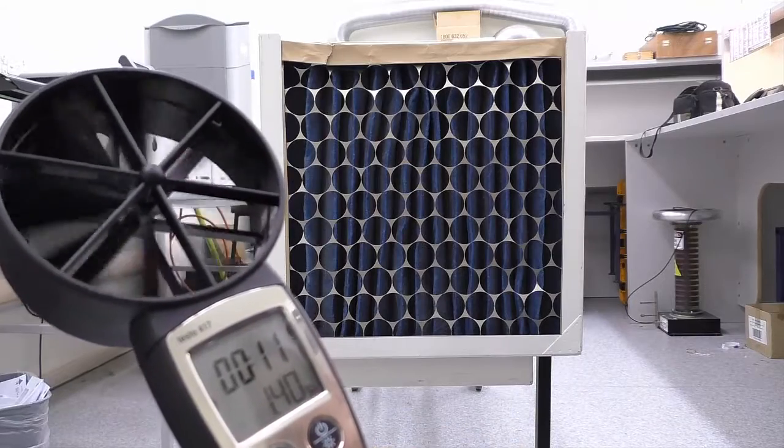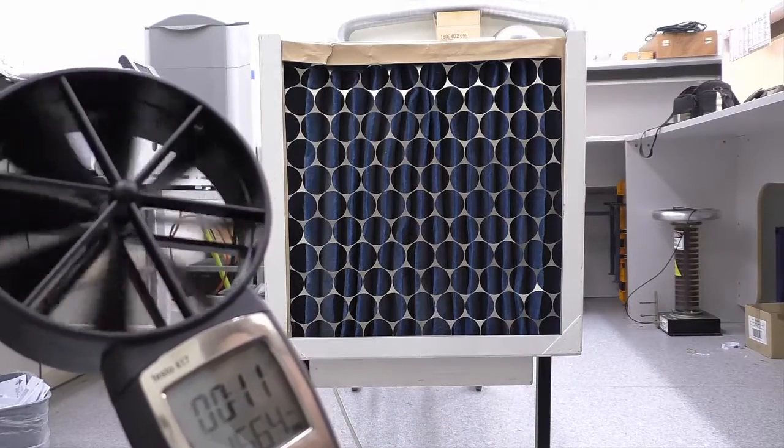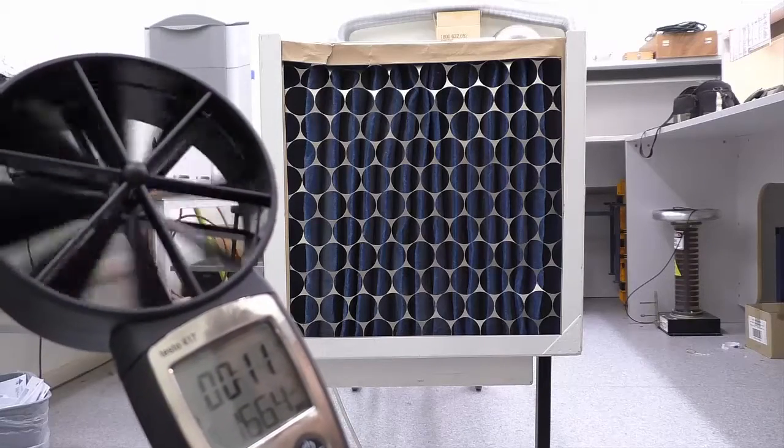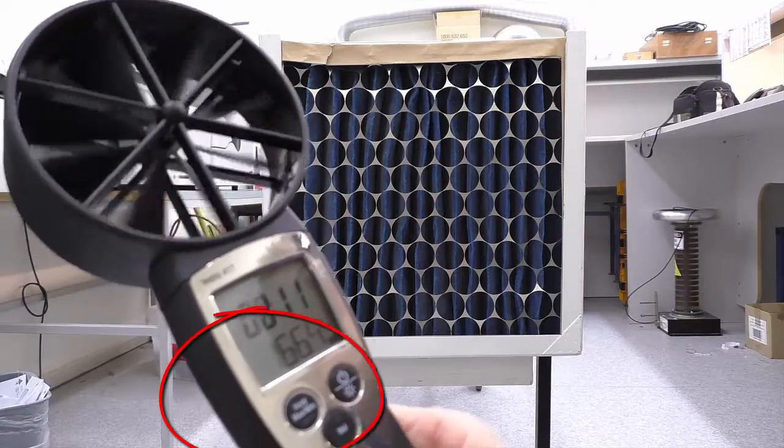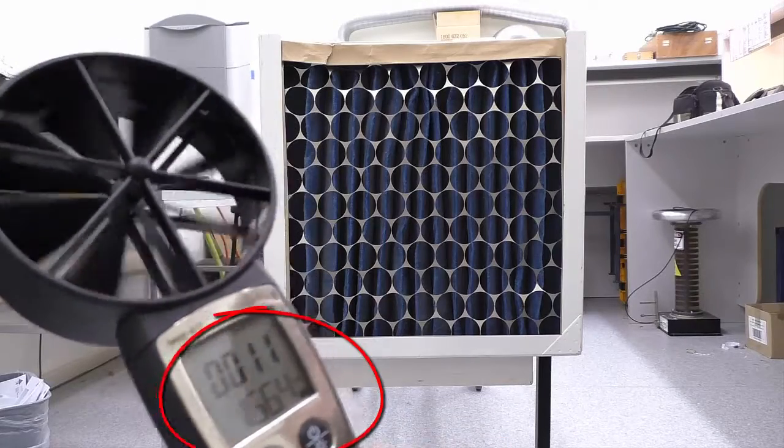I now push the mean button, which gives me a mean velocity. Now if I hit the volume button here, it will give me the volume, which is 166.4 liters per second, which is the throughput of this rig at that pressure.